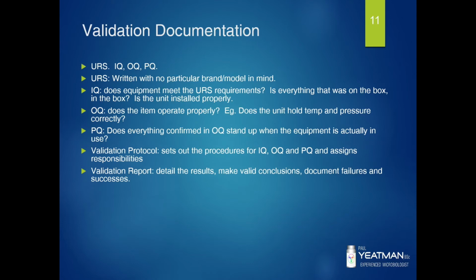And all this should be covered by a validation protocol which sets out the procedures and also assigns responsibilities. And following all of this work, there is a validation report which you'd want to write, which details the results, make valid conclusions based on those results, and also documents failures and successes. And of course, if there was a failure with any of your testing, you want to fully investigate it and justify why the equipment has been approved for use if that's what you deem a valid conclusion to be.